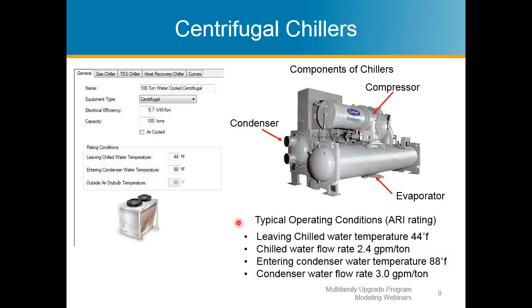What we see here, I wanted to show you, just like you have AHRI or ARI ratings for equipment, you'd go to the AHRI website. Well, for large units like this, you have ARI ratings, and you want to make sure you're getting information that is rated at these conditions. Typical operating conditions: your leaving chilled water temperature is 44 degrees. Chilled water flow rate is typically 2.4 gallons per minute per ton. Entering condensing water temperature is 88, the temperature of the water going out to the cooling tower. And your condenser water flow rate is typically 3 gallons per minute per ton.